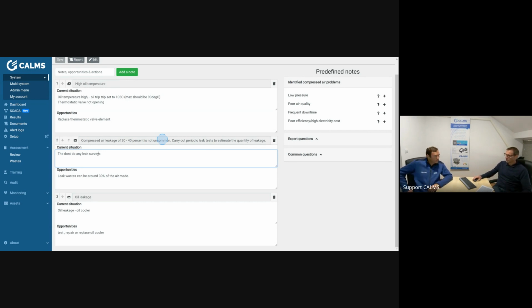Okay, but do you think they have some commonality with the pressure drop? Maybe they have. Maybe in your ring, with this machine, you have a huge leak, and so just in this part you have a pressure drop. Maybe. So just by fixing the leaks, I will not have to buy a new compressor, you think? This will be the guy that came to me selling the new compressor. He didn't mention this at all.